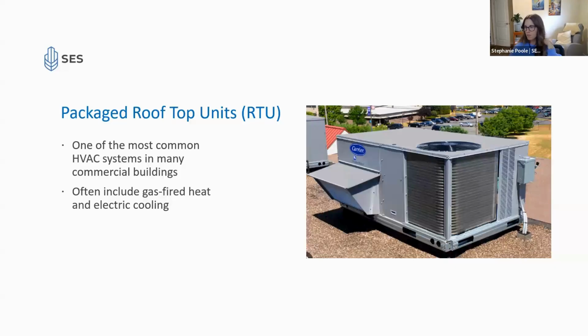Next slide. Okay, so I kind of explained this. And the one other thing to note that Ashley flagged early on is that many rooftop units, not all, but a good number of them will already have cooling in place. So they'll have gas heating and they'll have direct expansion cooling, which means that if you want to add a heat pump, you've already got electrical running up to that space. You've likely already got sufficient capacity because the heat pump's really not going to be that much bigger than the air conditioning piece. And that's why it's so easy to electrify these.